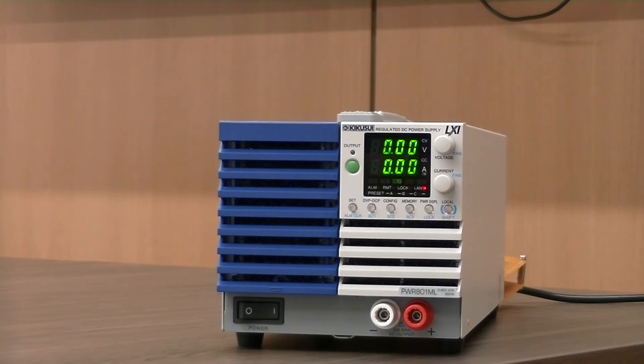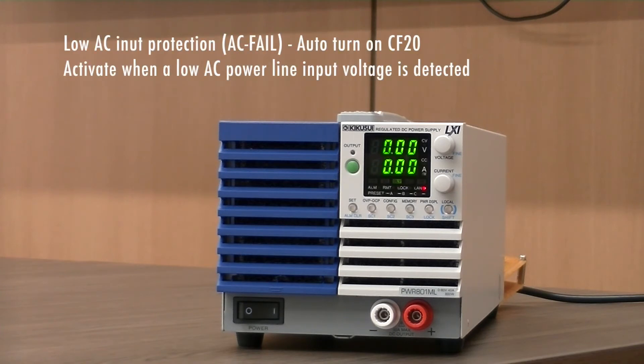The PWR01 can also sense when the AC input voltage is too low, causing the AC failed protection to activate and turn output off. You can set the PWR01 to automatically turn output on when the problem that caused the AC failed to be activated is corrected via config 20.